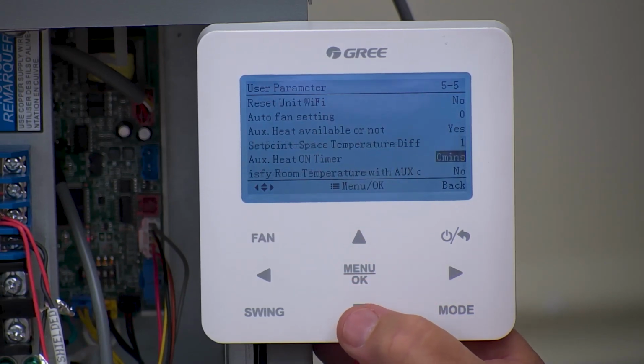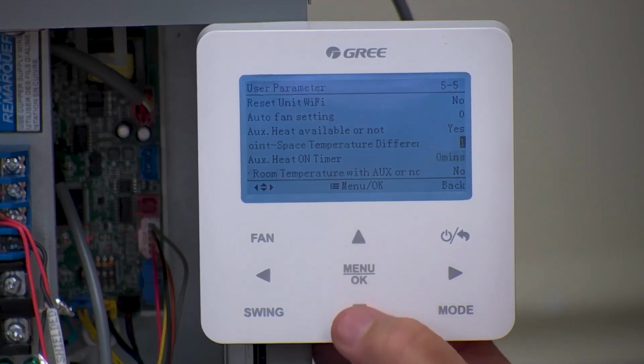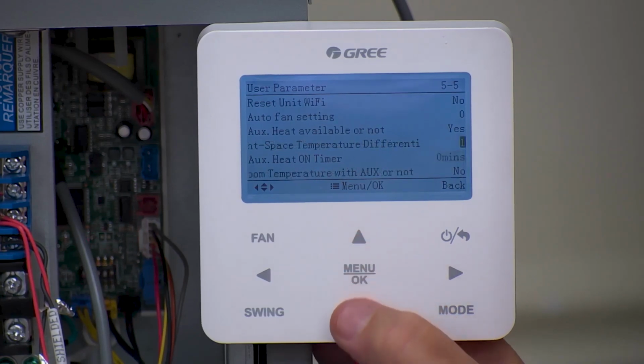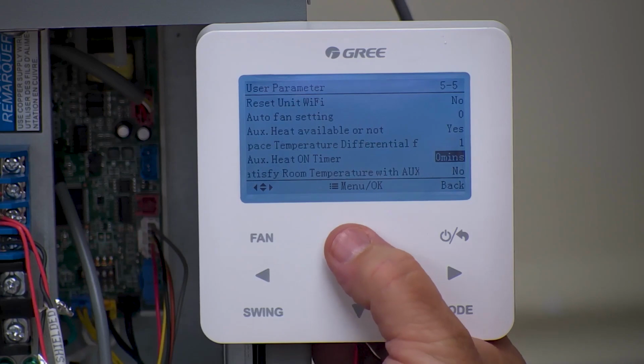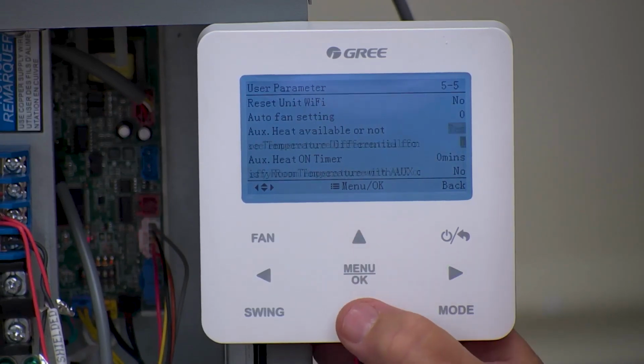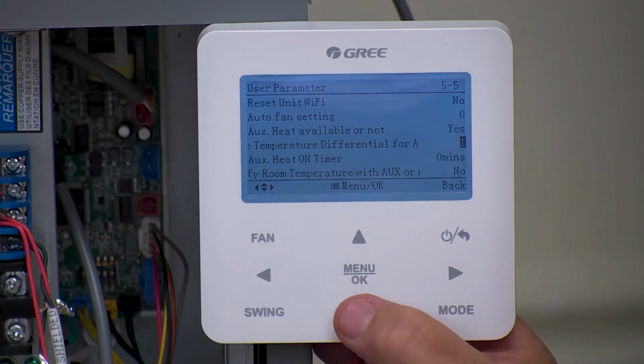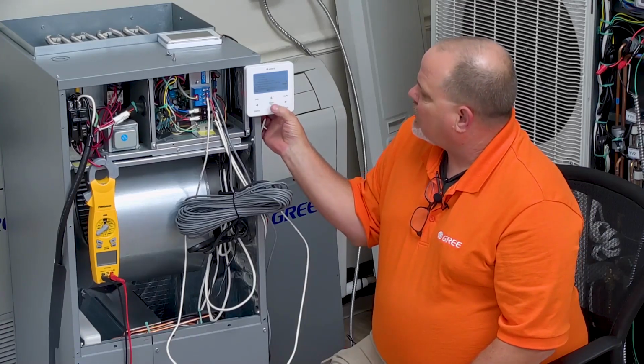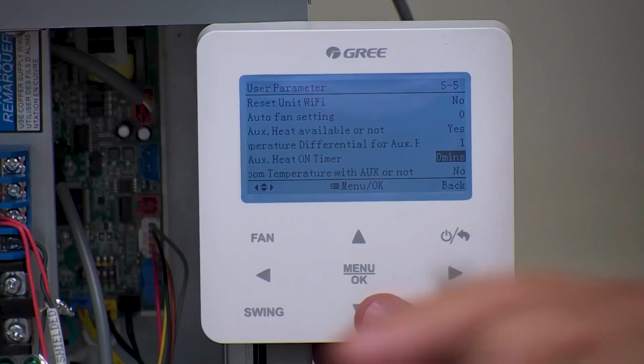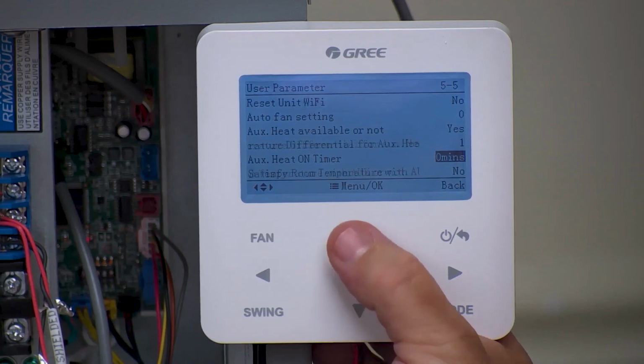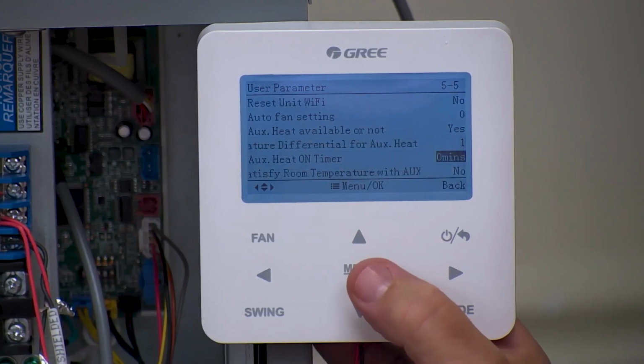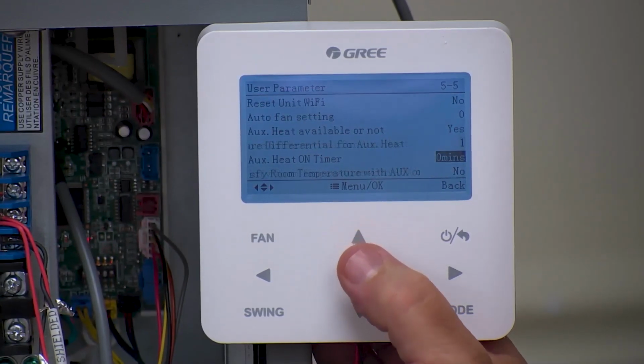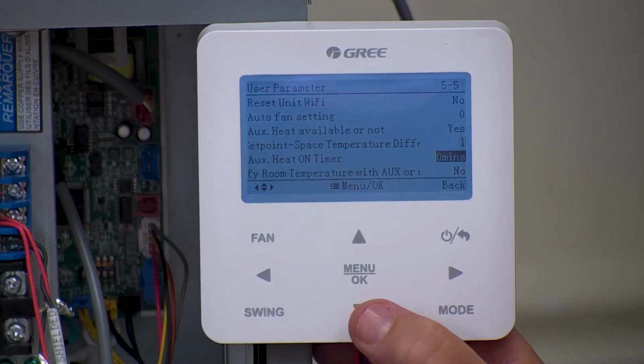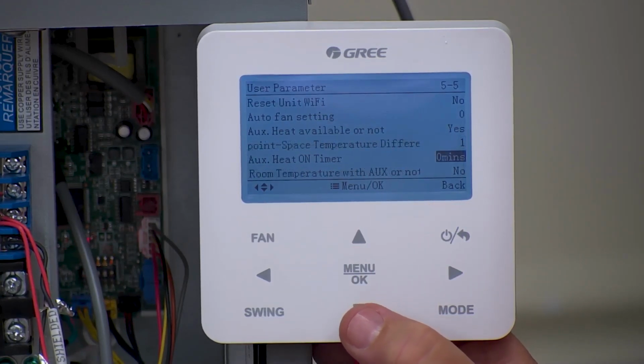As we go down a little further, auxiliary heat on timer, 0 minutes, you can set that from 0 to 60. Meaning you could actually set this up for, say, an older person like me, because I am getting old, right? And we inherently like to go to the thermostat and say, I'm cold, and we turn the temperature way up. Well, they're kind of defeating the purpose of having a heat pump, especially if it's 40 degrees outside. So what you can do with that timer is set it to 10 minutes. You can go 0 to 60. So let's say you set it at 15 minutes.